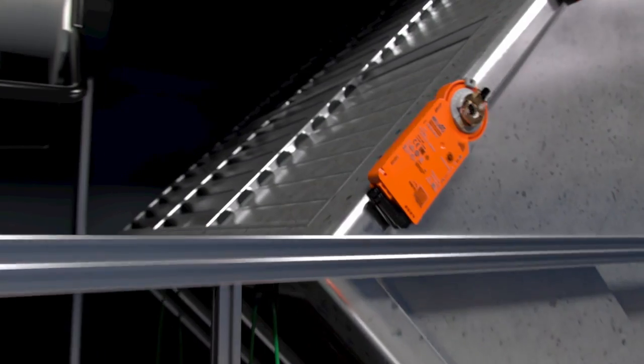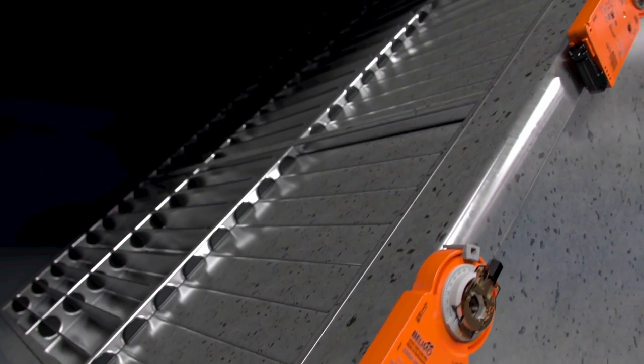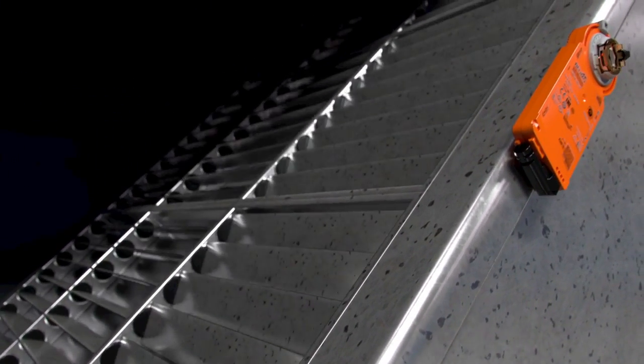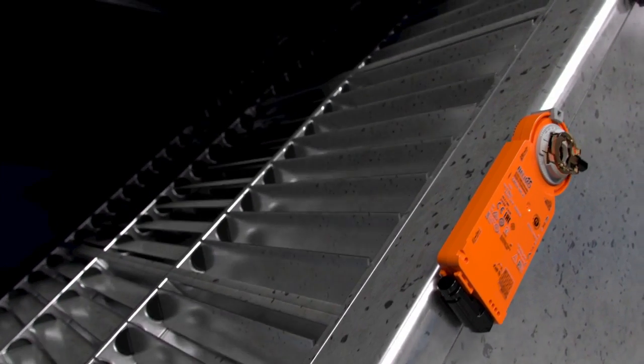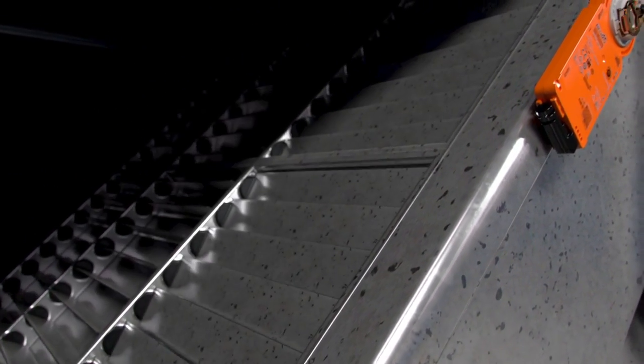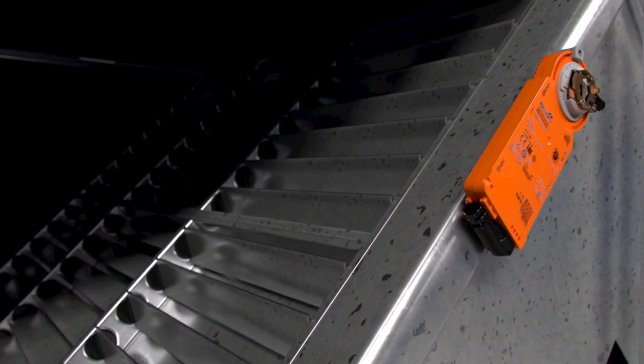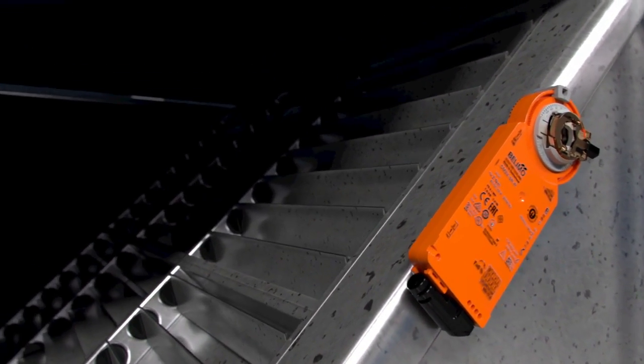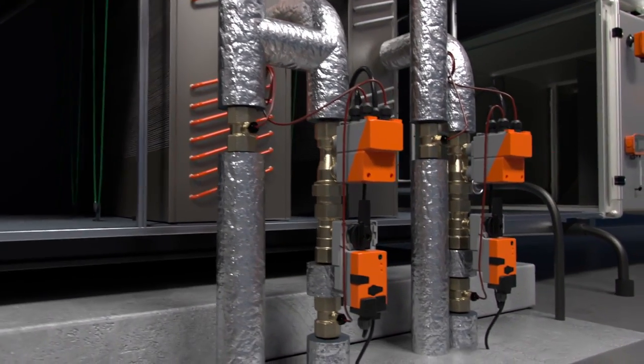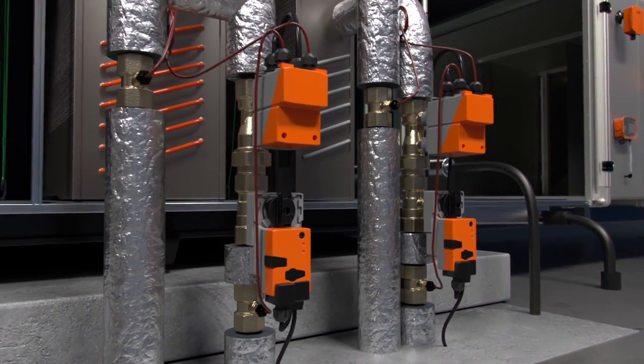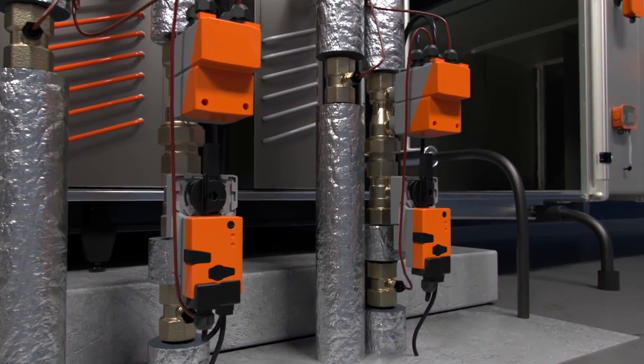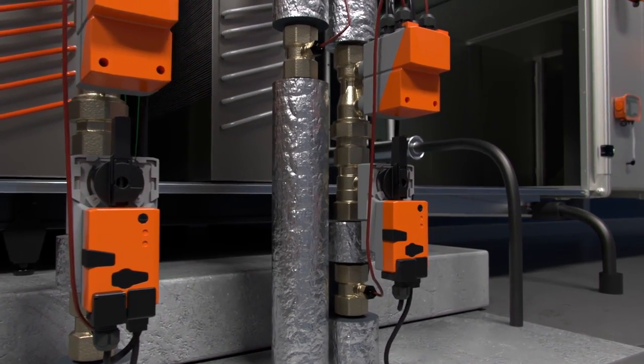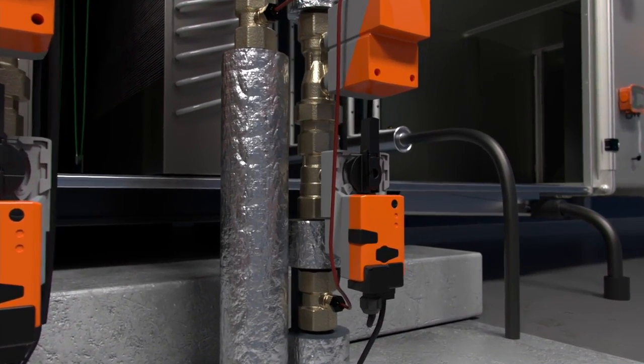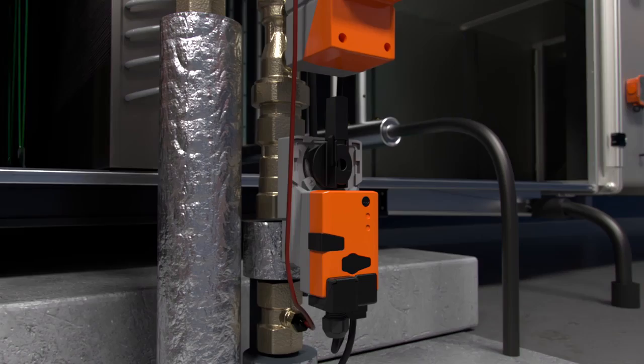Actuators can also be used to control the transfer capacity of the plate heat exchanger. By opening and closing the thermal bypass, either less or more heat is transferred from the extract air to the supply air. Control valves with actuators control the supply of cold or hot water to air coolers or air heaters. The power output of the heat exchanger is ensured by demand-based flow or power control.